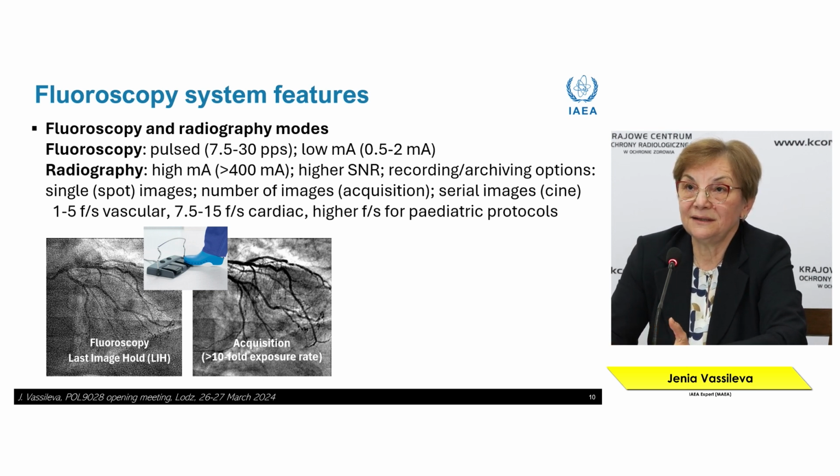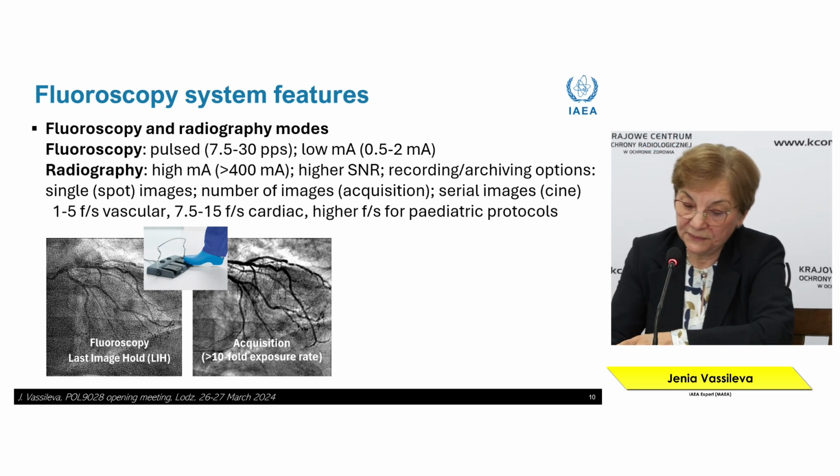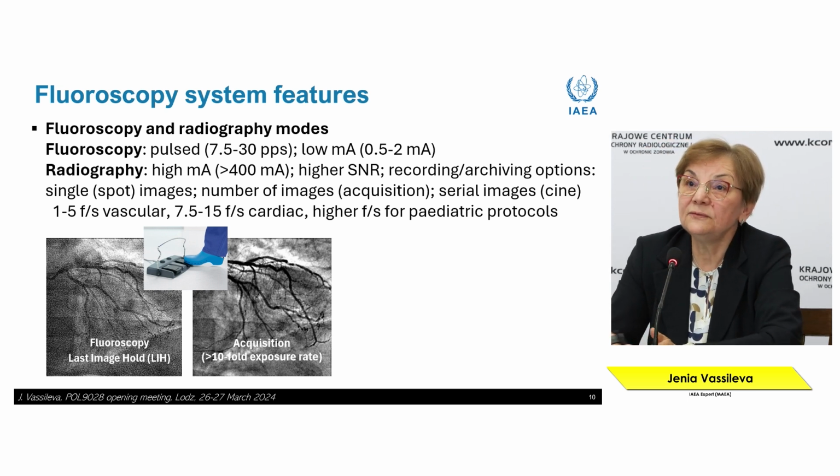So I was very happy to listen from the previous speaker about the use of 2 different modes, fluoroscopy and DSA, or in fact, acquisition dose radiography. And every interventionalist should know that the use of acquisition, it's just tapping on the other pedal of the control pedals of the fluoroscopy system, increases the dose rate at least 10 times.